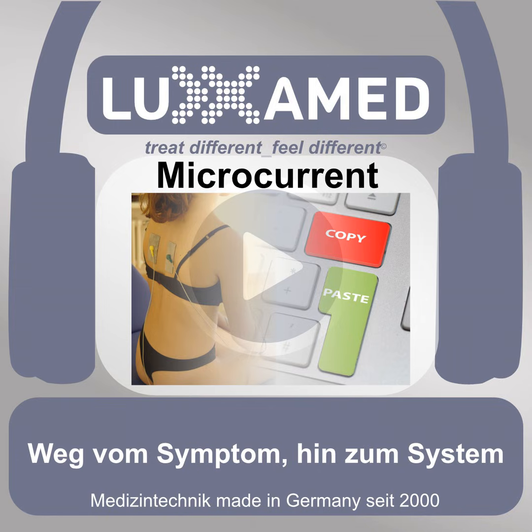And in practice, however, it turns out, with automated systems like the Luxamed, for example, this polarity de facto no longer plays a role. If only because in our automatic mode, we don't use constant fixed polarities at all. And the device automatically determines this polarity in automatic mode via the feedback process, via the therapy algorithm.